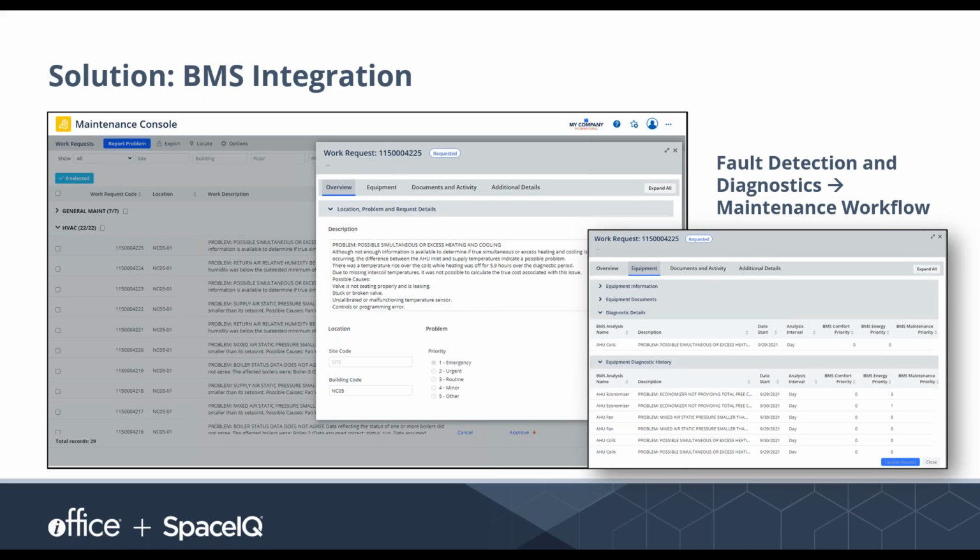We are able to bring that information into Archibus and share that within both diagnostic history and in the maintenance console, where we will take diagnostics that meet a certain threshold of priority and automatically create work for them. So while Clockworks does the diagnostics, they're looking to Archibus to provide the workflow, what happens after something is detected that needs attention. And that will go right into work requests, where that obeys the SLAs and goes right to the right person in the field to work on it.